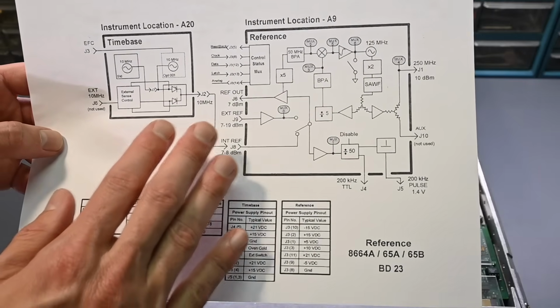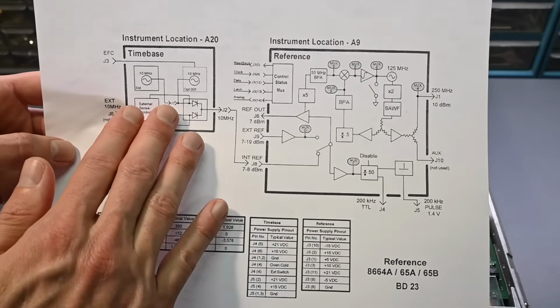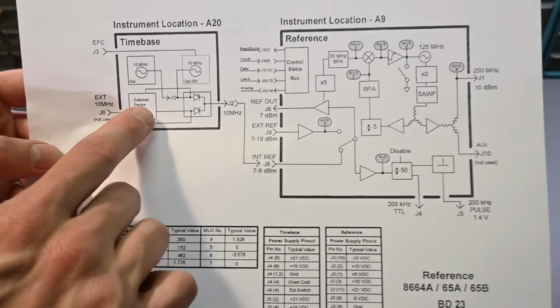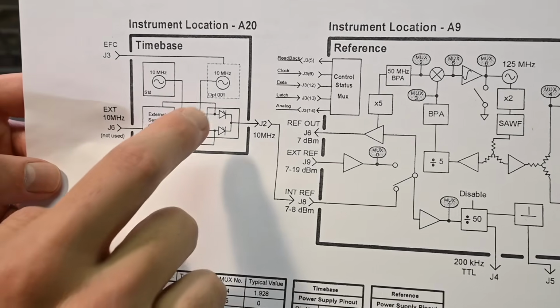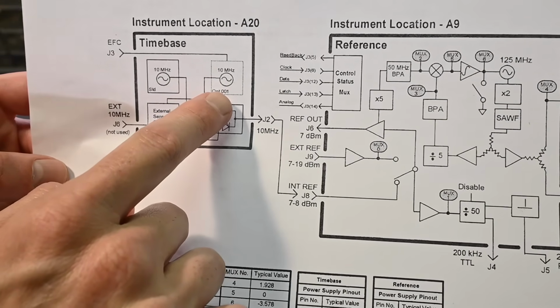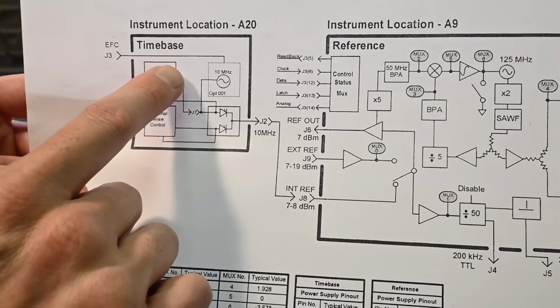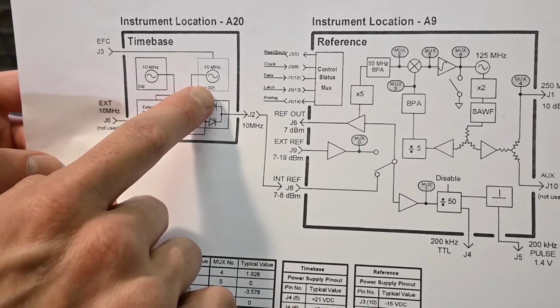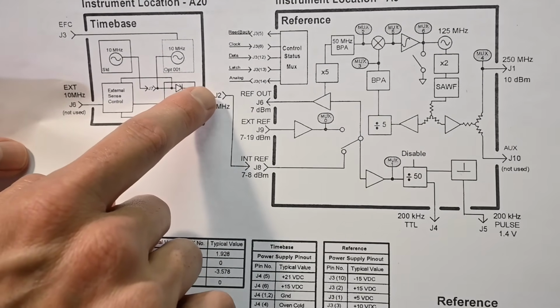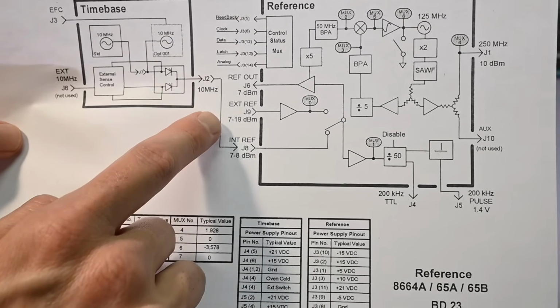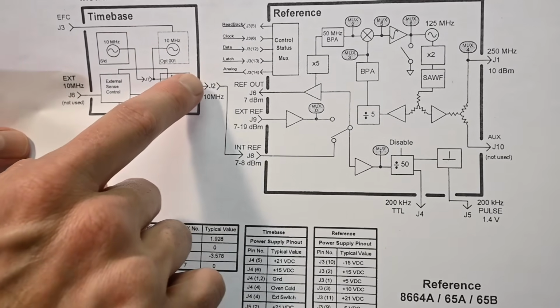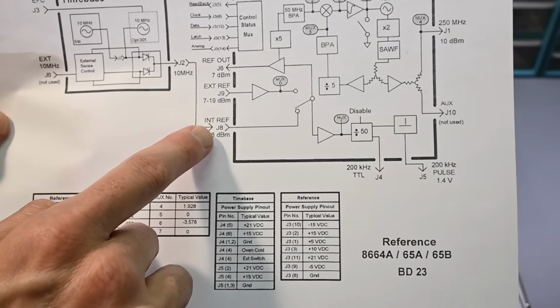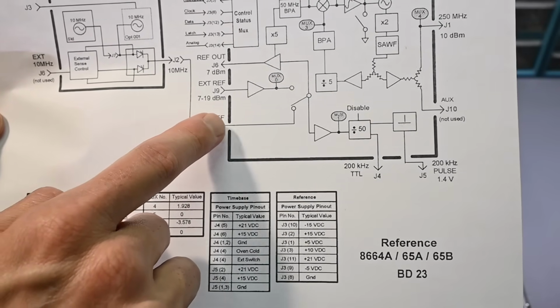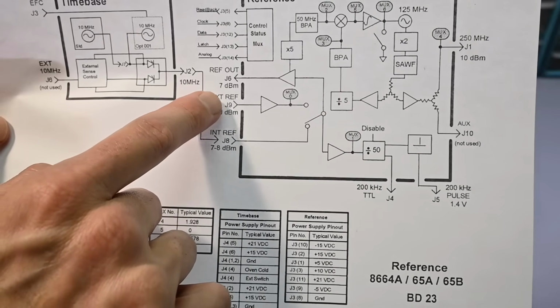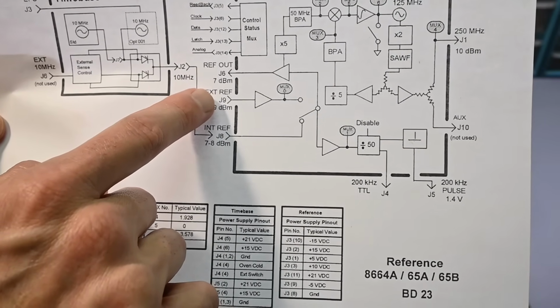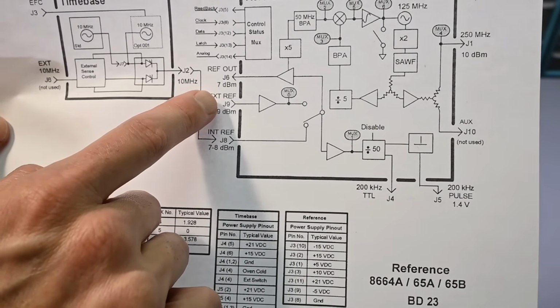But anyway, on this block diagram here, this is the section for the time base or the reference oscillator. And you can see right here, bring this up a little bit closer, they do show option 1, the 10 megahertz reference right there, and then here's the standard reference. And what they're showing is that the two would join together, and then we have an amplifier probably acting like a buffer. So over here it says 10 megahertz. Now this connection that's coming over here, I'm assuming would be inside the instrument because there's nothing on the back panel that says internal reference going in. There's an external reference, and that's this connection right here. So you can provide your own external reference time base.